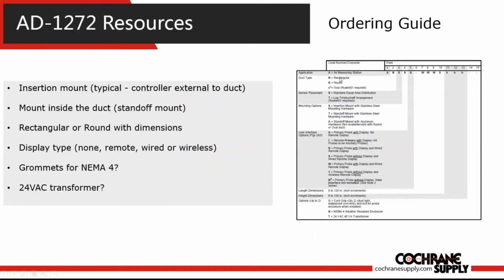You can decide whether you want a rectangle or a round installation. Obviously, it's decided by the ductwork on the job site. Do you want to mount it internally inside the duct, or do you want to insert it and have a controller on the outside? Do you want a display that's remote or not? Do you want NEMA 4? Really very simple to specify this product. Duct, you can tell us what that is. We ask a couple of questions and give you a part number, and you can quote the job.